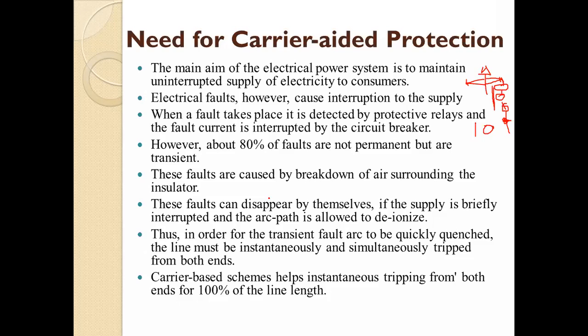will get immediately disconnected. Okay, then carrier based schemes helps instantaneous tripping from both ends for 100% of the line length. Okay, so this carrier based scheme means carrier aided protection helps instantaneous tripping. So what happens? It gives instantaneous tripping from both ends and for the 100% of line length. Okay, so when we are considering the zone 1, zone 2 and zone 3 protection, in zone 1 protection, what we are doing? We are actually using the 80% only line length. We are covering only 80% length. But here we are covering 100% line length.